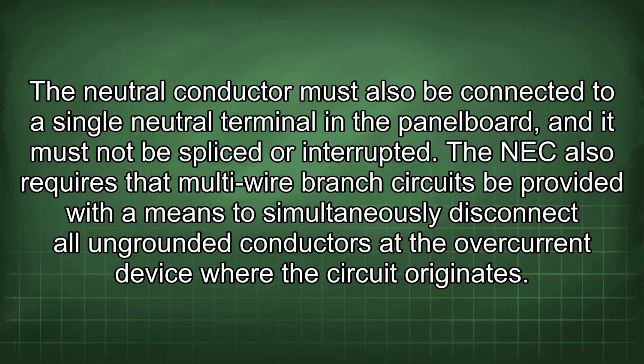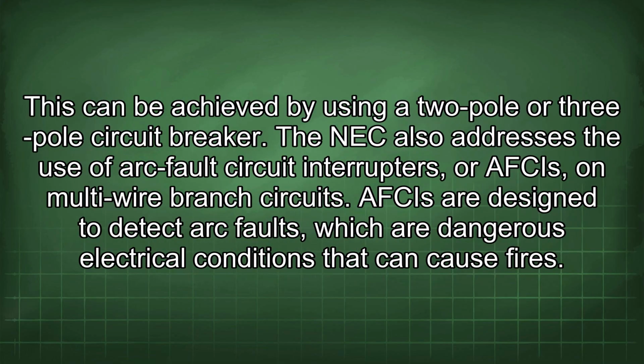The NEC also requires that multi-wire branch circuits be provided with a means to simultaneously disconnect all ungrounded conductors at the overcurrent device where the circuit originates. This can be achieved by using a 2-pole or 3-pole circuit breaker. The NEC also addresses the use of arc fault circuit interrupters, or AFCIs, on multi-wire branch circuits.